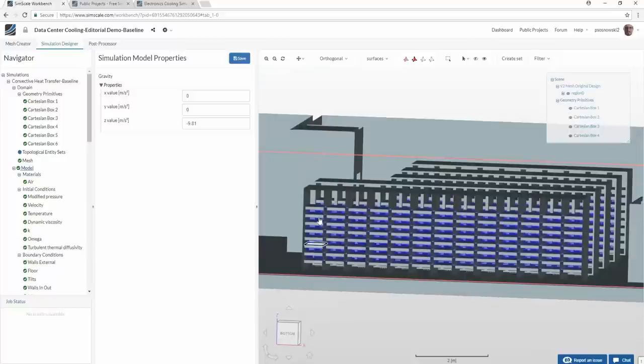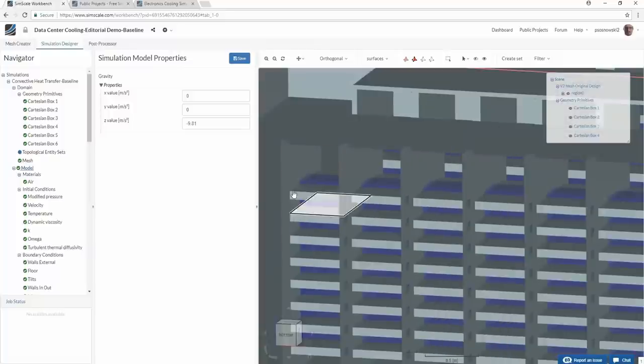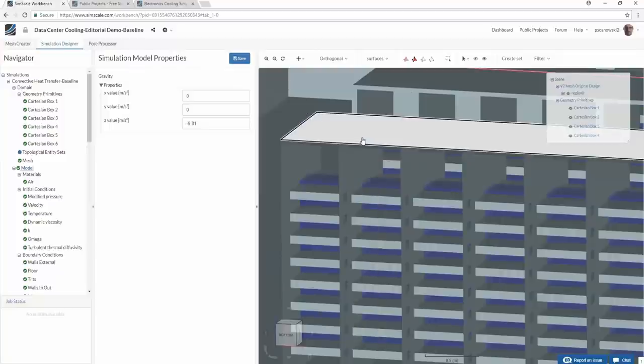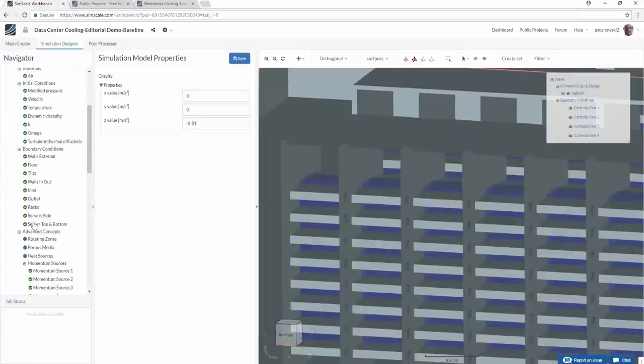But unfortunately, if you were to simulate the presence of the fan itself as a boundary condition, you would have to consider the fan as a black box. So there would be a suction outlet and a velocity inlet, for example. The problem with that is that you cannot maintain continuity of the flow. If we have a hot flow on this side and we're pushing it through the fan itself, if you're sucking the air out, it's going to the void, and then it's being introduced with a different velocity. So this kind of joint inlet and outlet sections are not supported yet. And at the moment, you would need to use the momentum source approach.